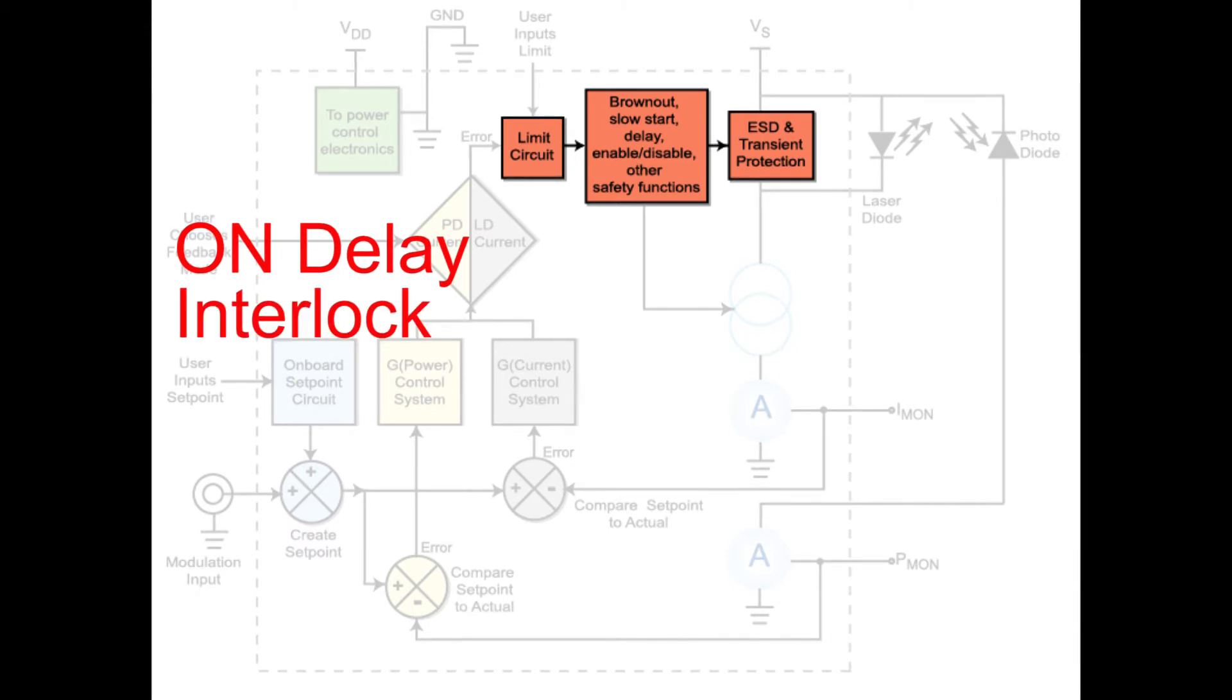Second, there must be a way to interlock protective housings or entry doors, so that if the housing or door is opened, the laser shuts off. Laser diodes are sensitive to thermal shock, so a slow start circuit is usually integrated.